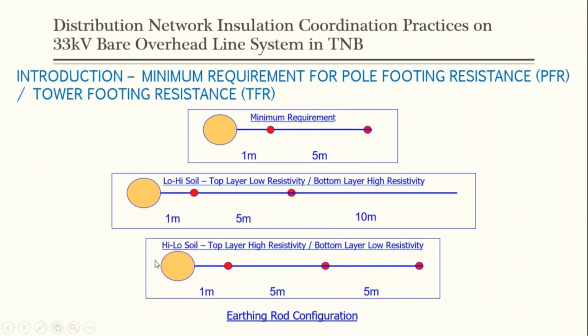And for high-low soil, the top layer has high resistivity and the bottom layer has low resistivity. So the configuration is a bit different, where we have 1 meter counterpoise tape, and then we drive the copper rod to the ground, and then another 5 meters spacing, another copper rod, and another spacing of 5 meter. We have another copper rod. So these would be the three minimum requirement for pole footing resistance and tower footing resistance configuration.